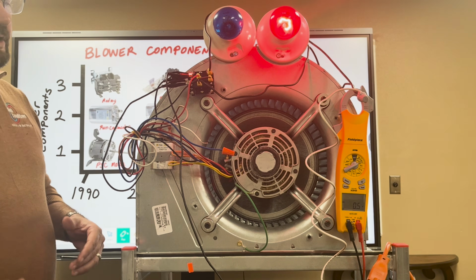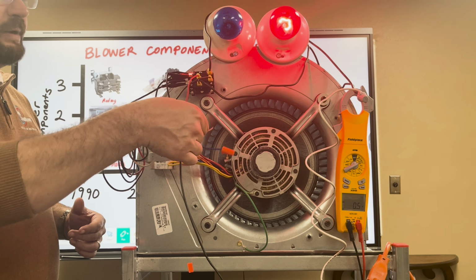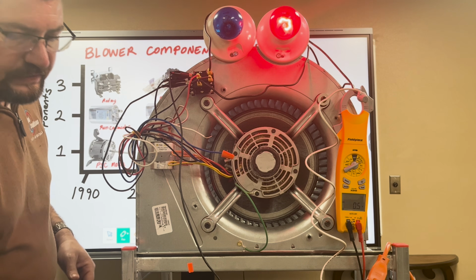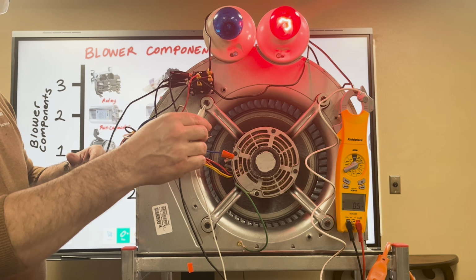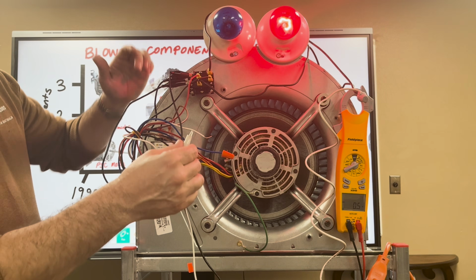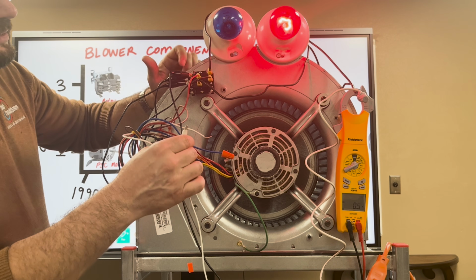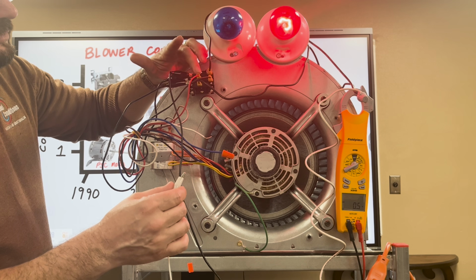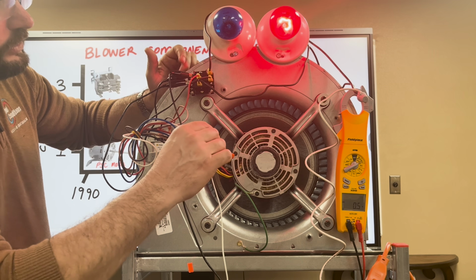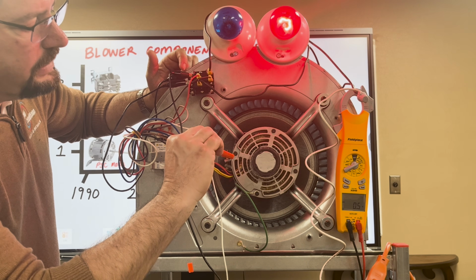As far as the motor goes, we're missing a full leg of power. We need to put the second leg of power there. Once I do this, you'll see that speed, which is wired up here—the red wire is wired to the normally closed, that is low speed—so low speed's going to run.